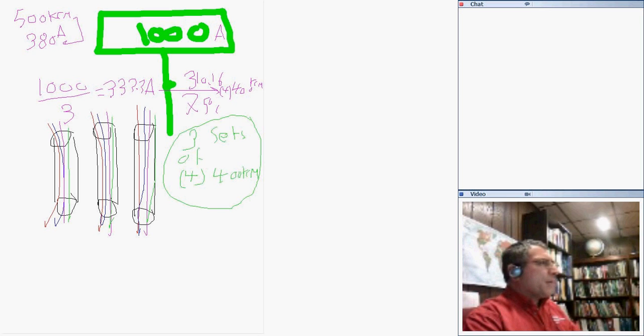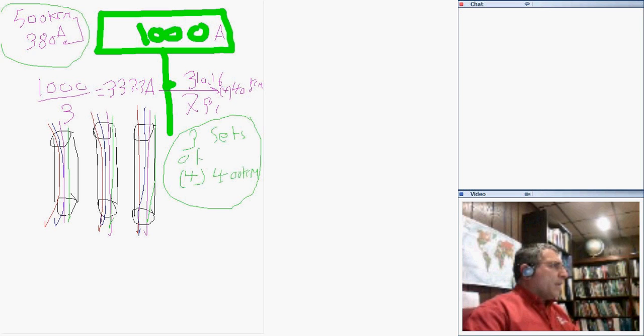Any question, guys, about paralleling conductors? Why parallel? Because it's too big of a conductor to carry. What are the rules for paralleling from your friend Chad? Here are my rules. If I can't carry the load with 500 kcm, I parallel. Or if it is more than 380 amps, I parallel. Well, 400 amps, basically. If my panels are more than 400 amps, I parallel, no questions asked. Any questions?